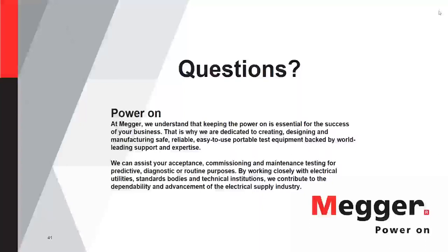But the battery does have a limited lifespan. And with a flooded lead acid cell, typically when it starts approaching end of life, you will see a change of about 50 to 100% on your ohmic tests from the baseline value. That is a typical measurement. Okay, I think that's it for that question? Yes. All right, I'll go ahead and move on to the next one.